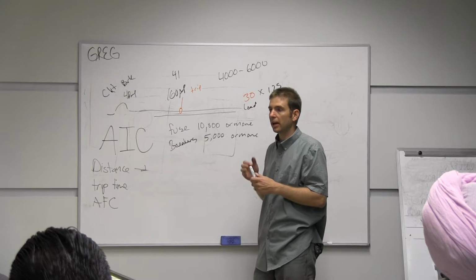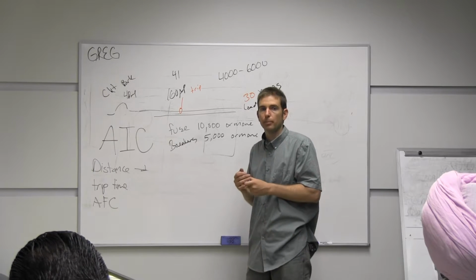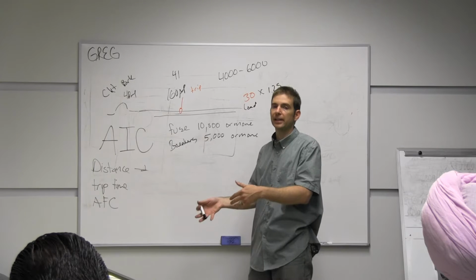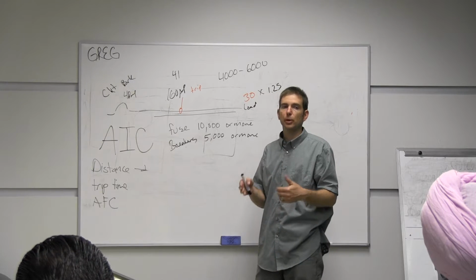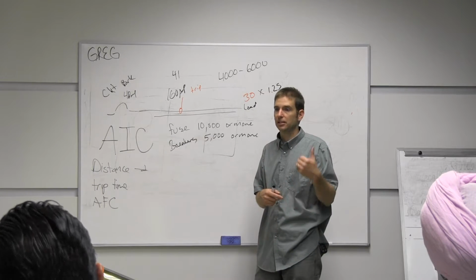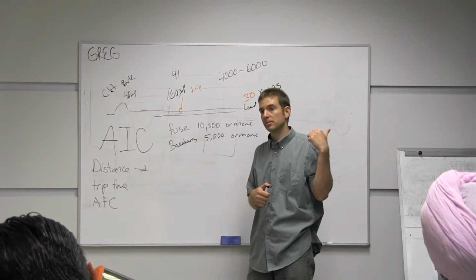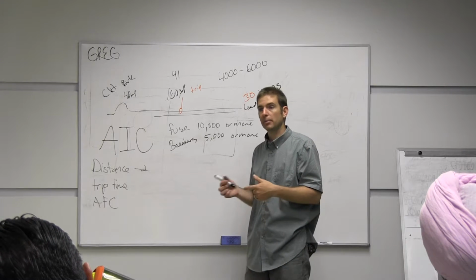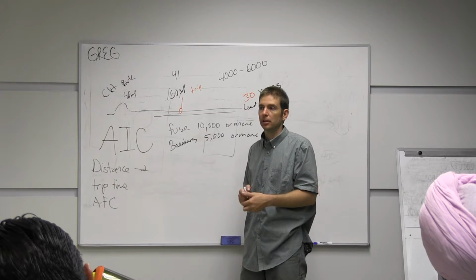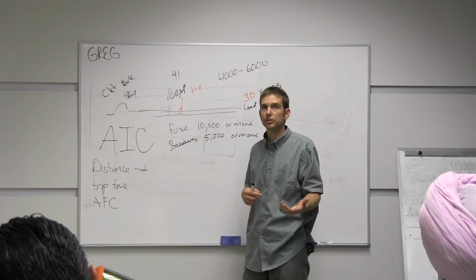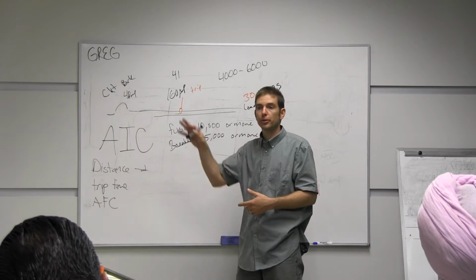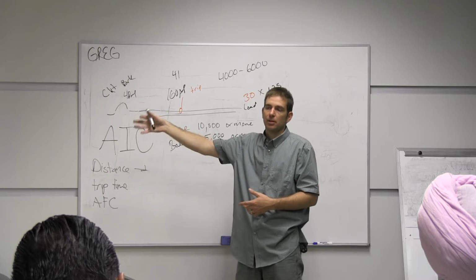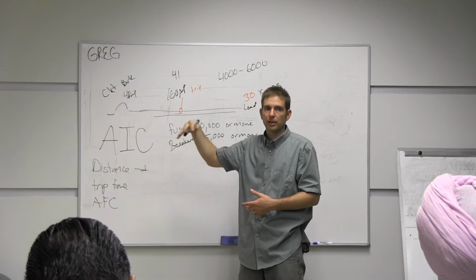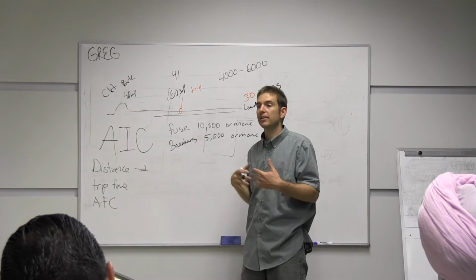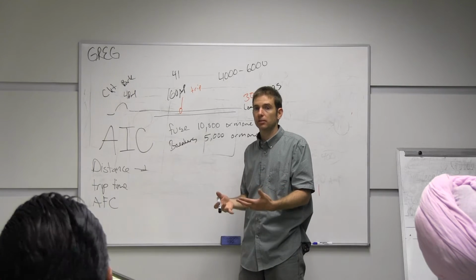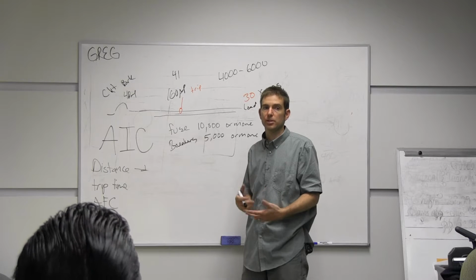So we have to be real careful about making changes, or when we do repairs, we want to repair things as close as possible to the way they were installed originally. Because after 70 years, it's kind of a nightmare. When you come here and you see a brand new facility, you see brand new electronics, like raceways, new conductors. Although you're really close to the coast and you're going to have damage from the coastal conditions, everything's new. So when things do fail, replace it the way it was originally, please.